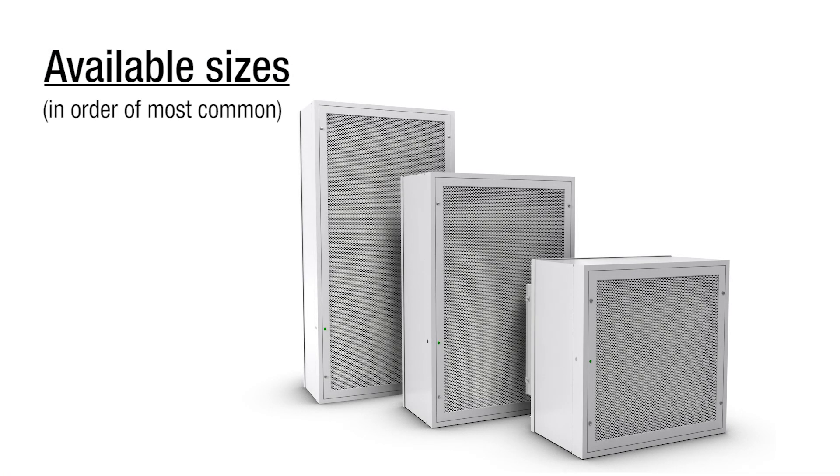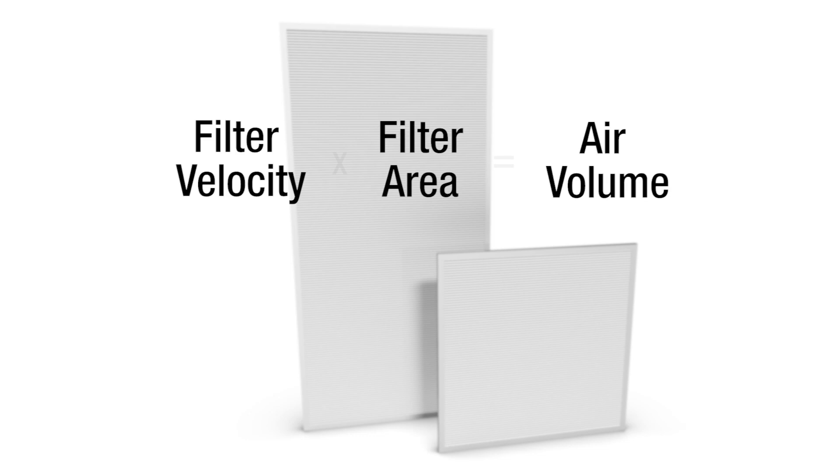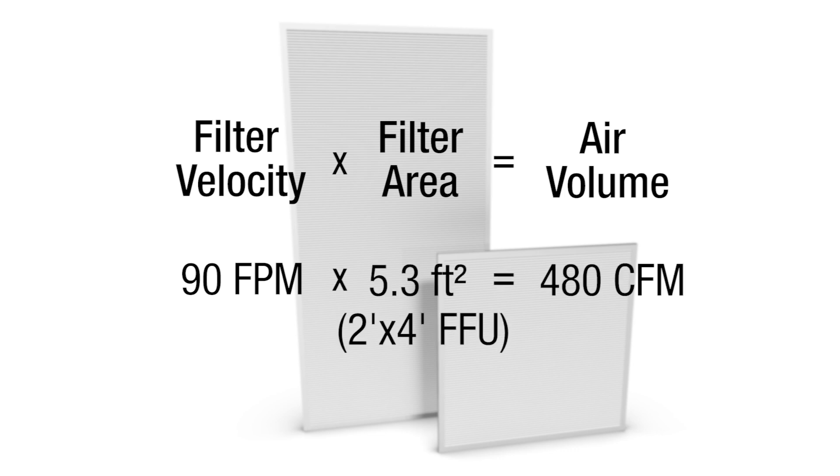FFUs are typically available in three sizes: 2' x 4', 2' x 2', and 2' x 3', and are designed to fit into a standard suspended ceiling grid. FFUs are typically sized for 90-100 feet per minute filter velocity. For the most popular size of 2' x 4', this equates to 480 CFM for a room-side replaceable filter model.